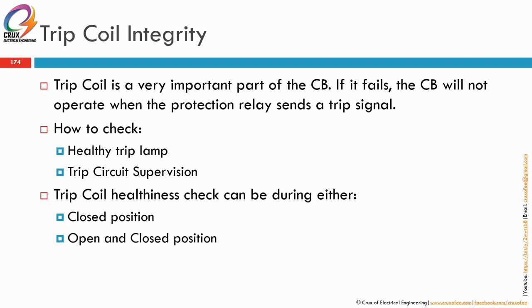So under any condition, your trip circuit supervision must be healthy, especially in the closed condition, and also the trip coil is ready lah to trip. So this trip coil supervision is to monitor the condition of the trip coil. The trip coil can be checked either during the closed position, or during both the open and closed position. Most low voltage and up to a certain medium voltage is only monitored under the closed position. But when you go to higher voltage, where it's more critical, 33 or 132 kV and above, it will monitor the trip coil in both open and closed position.